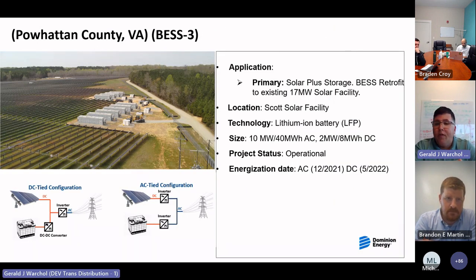Coming to a fast stop, we're looking at BESS pilot project number 3, a very unique project. We talked about the intermittency of solar. This project has two components: a DC coupled component and an AC coupled component. If I tie the battery energy storage system directly with the DC solar array, I can provide smoothing by controlling that upstream set point, making sure it always gives me 8 megawatts, and when clouds come over, taking power from the battery instead. This project tested and proved that technique to be accurate. We also have an AC coupled component. The AC side is 10 megawatts, 40 megawatt hours, and the DC side is 2 megawatts, 8 megawatt hours.